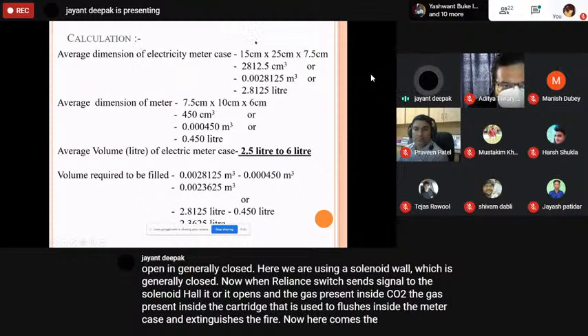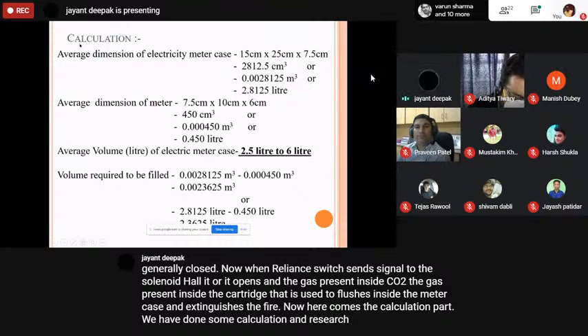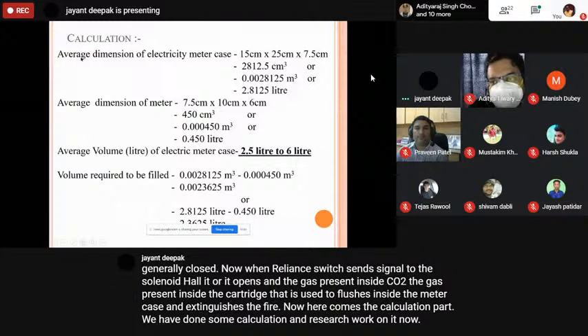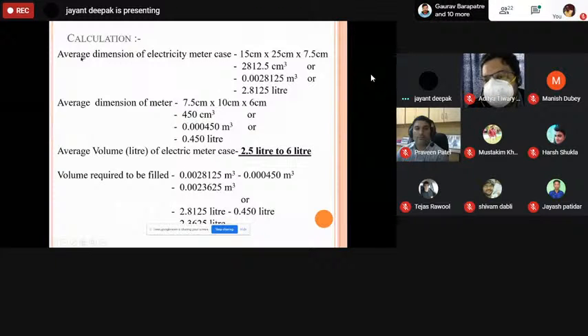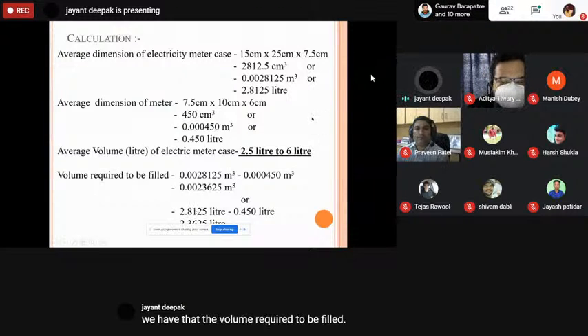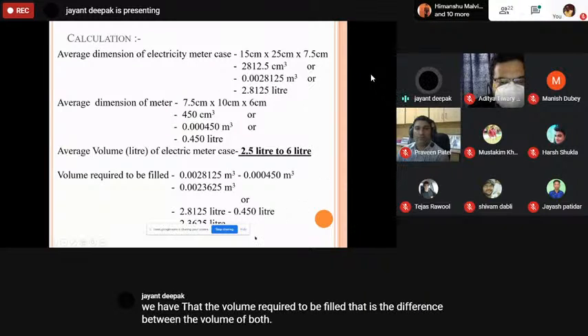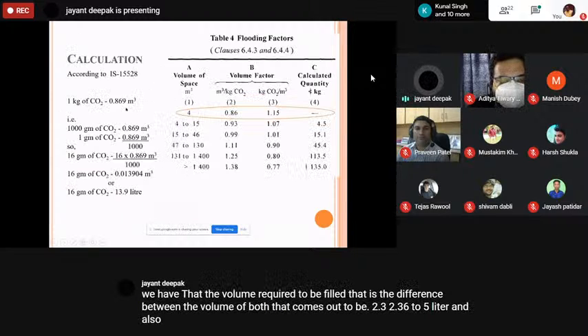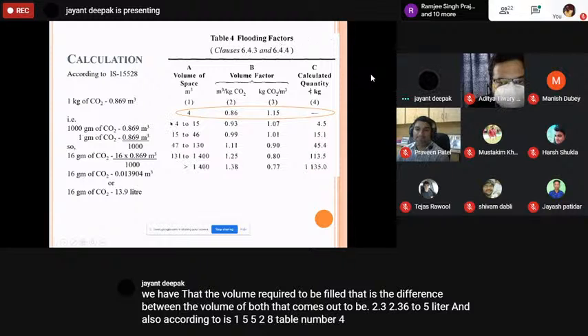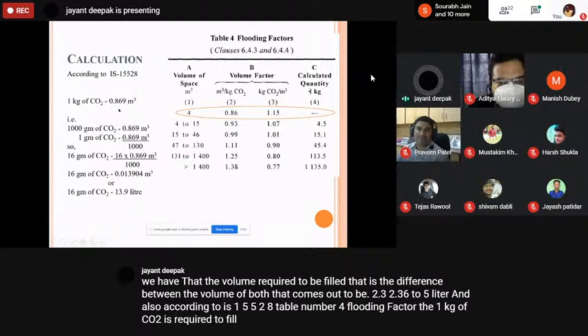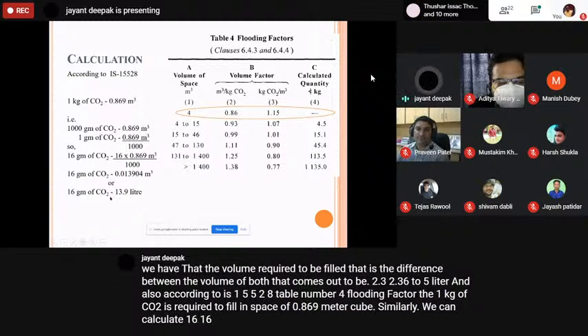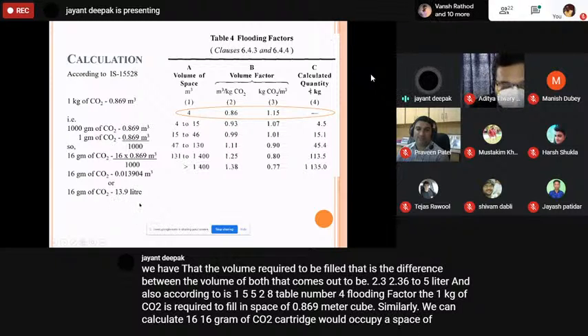Now here comes the calculation part. We have done some calculation and research work on it. The volume required to be filled, that is the difference between the volume of both, comes out to be 2.3625 liter. And according to IS 15528 table number 4 flooding factor, 1 kg of CO2 is required to fill a space of 0.869 meter cube. Similarly, we can calculate that a 16 gram CO2 cartridge would occupy a space of 13.99 liter.